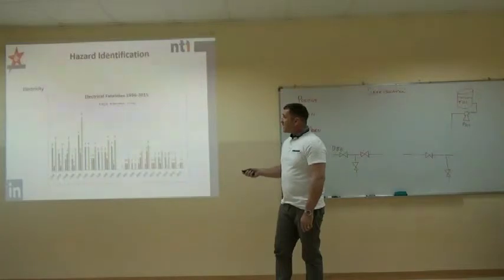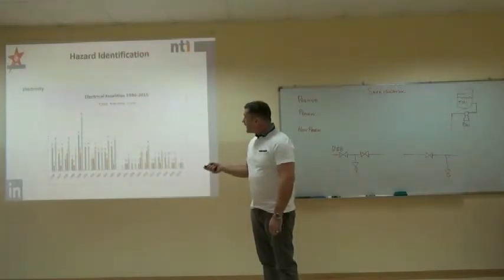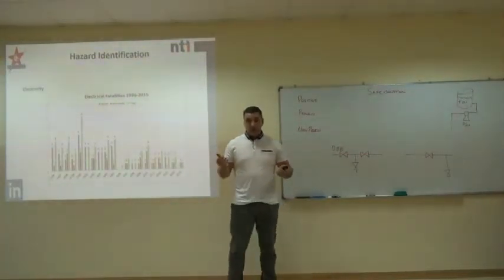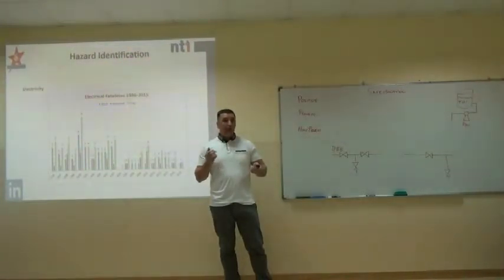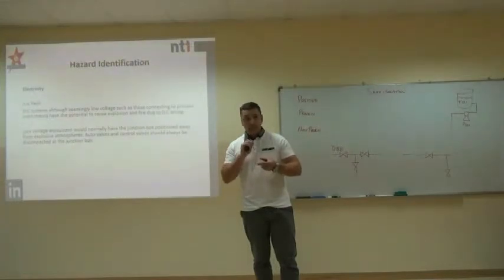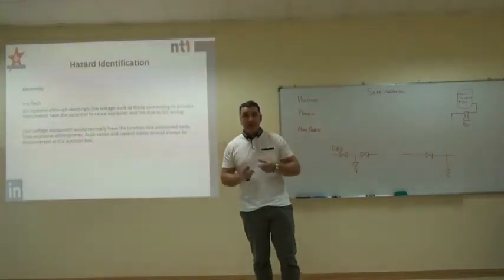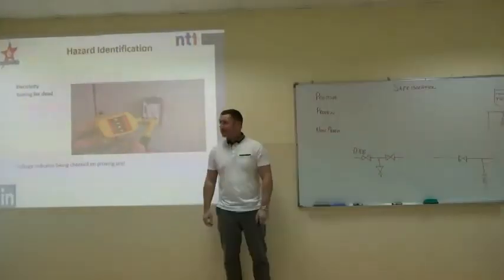Electricity. This is a graph of electrical fatalities in the UK — blue is at work and red is non-work. We know the dangers of high-voltage AC: it causes burns to our body, it effectively stops our heart from beating and causes ventricular fibrillation — effectively giving us a heart attack or extreme burns. Low voltage DC causes DC arcing, which is an ignition source. We're working in an explosive environment. We must always treat low-voltage DC with respect, make sure it's isolated correctly, and to eliminate that hazardous energy we test for dead.